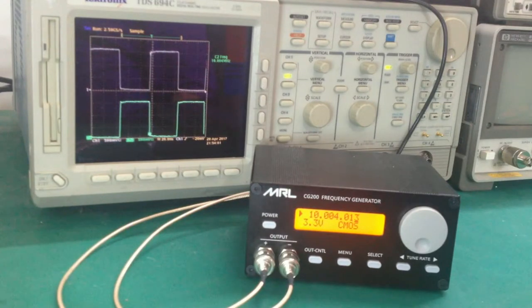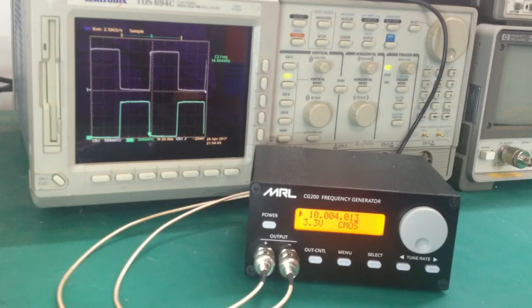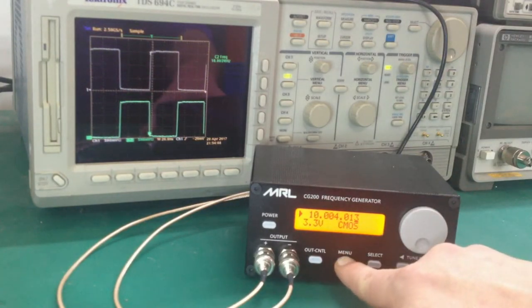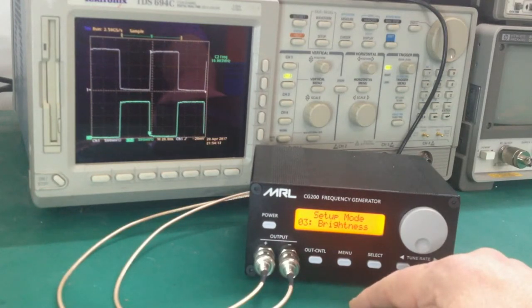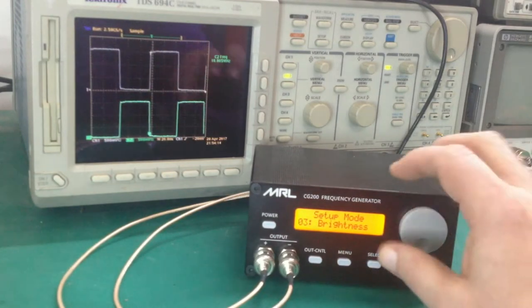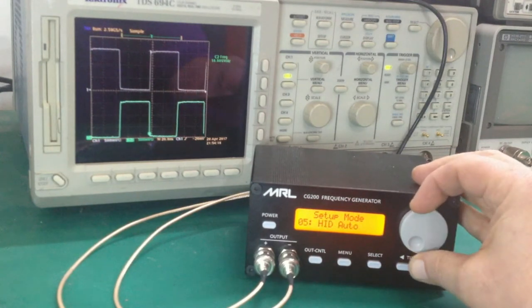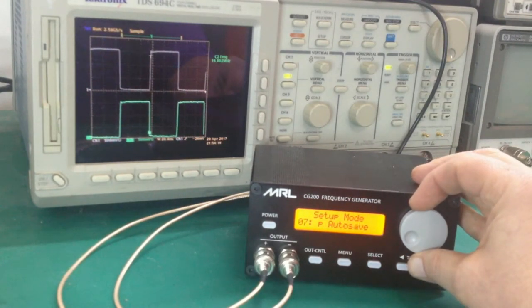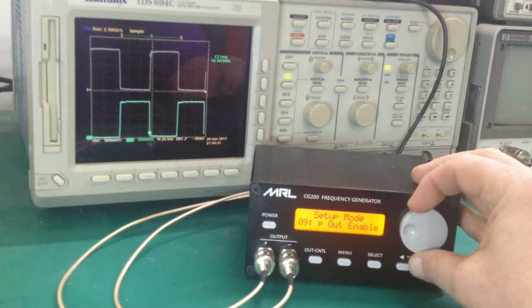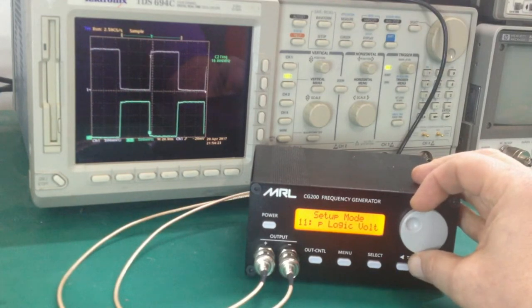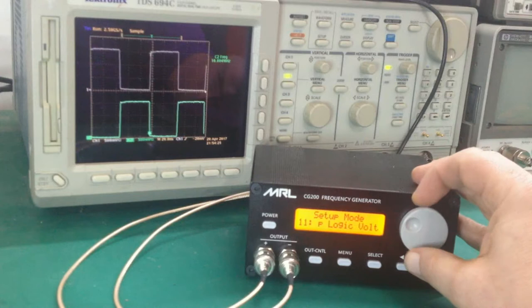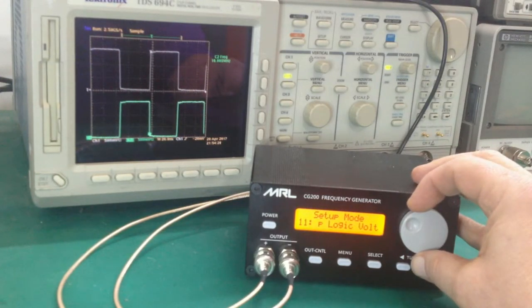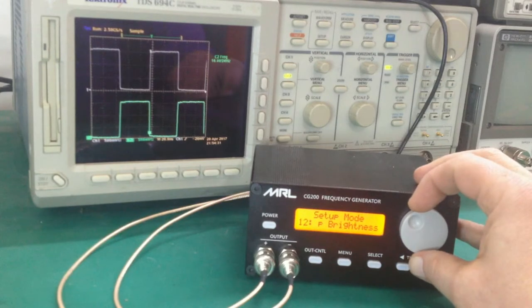There is a front panel menu control operation that has about 20-something items in menus, and several normal ones you would expect, like brightness and the display form, whether you want commas or dots, depending on whether you have a more European or North American bent on your display. You can go down to the power-up settings that control how you want this unit to come up when it first gets powered.